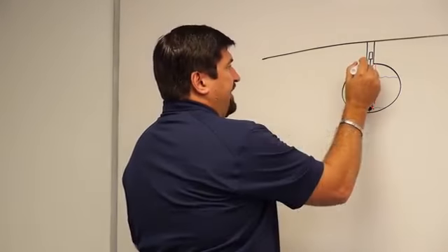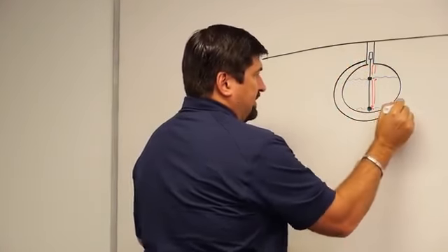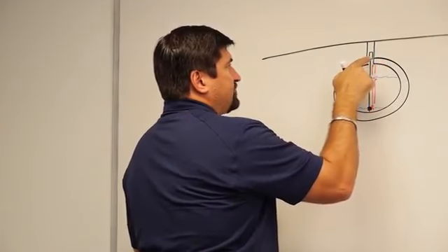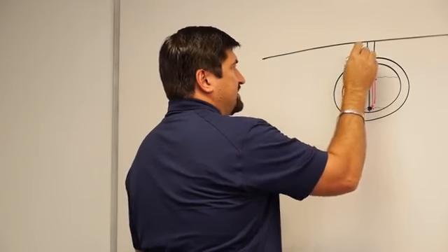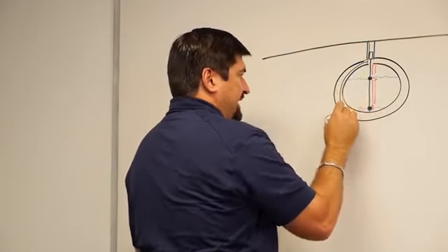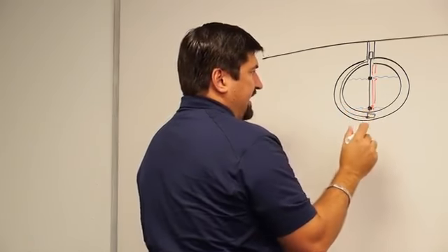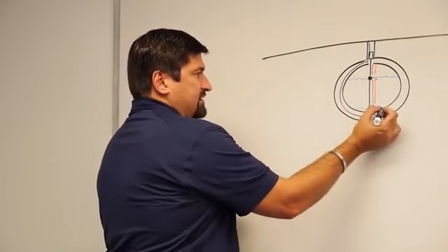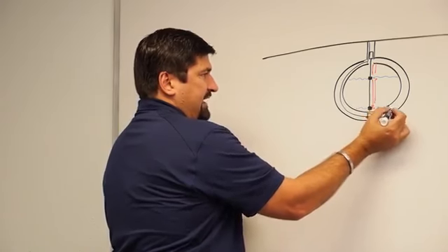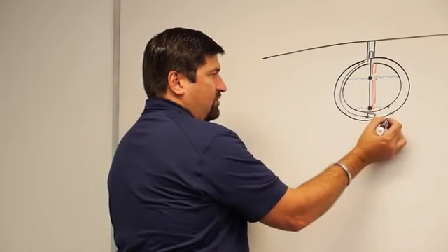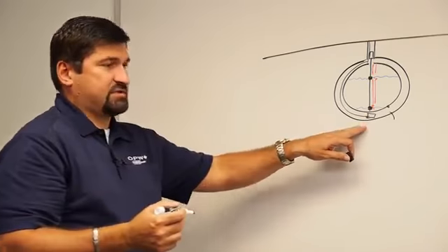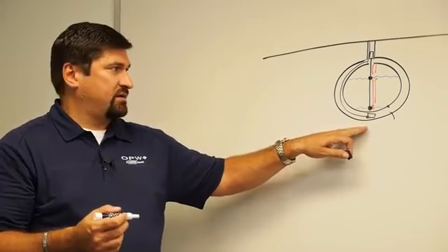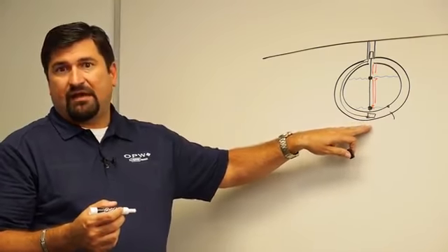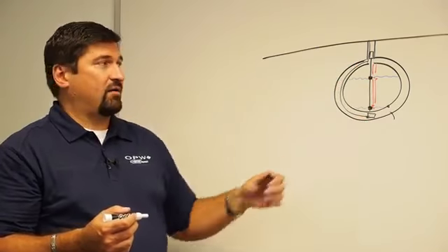Well, the next thing that an ATG will do is that if I have a double wall tank, basically where I have the ability to put a sensor in the annular space at the bottom of the tank, what it's doing is looking for a breach in the inner tank to the outer wall or from the outer wall in. And all this is just a float type sensor or an optical sensor that's basically telling you that you have a problem either in the inner or the outer wall.